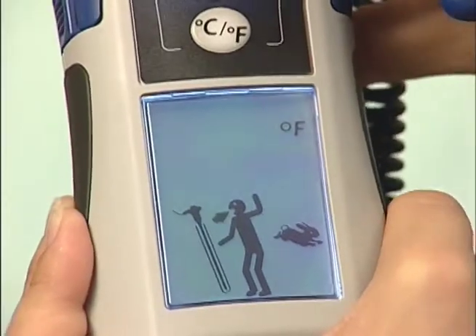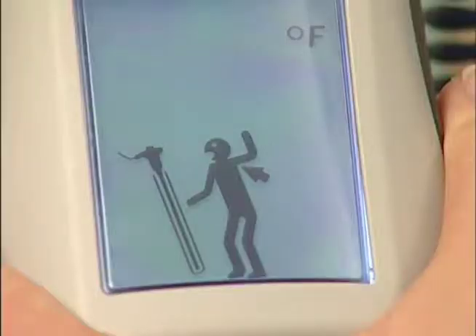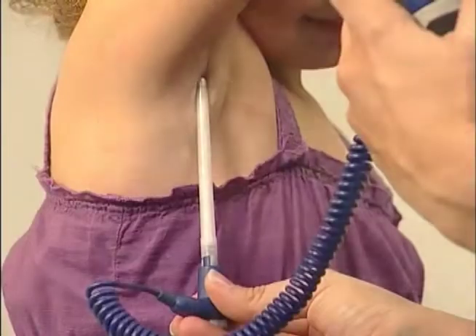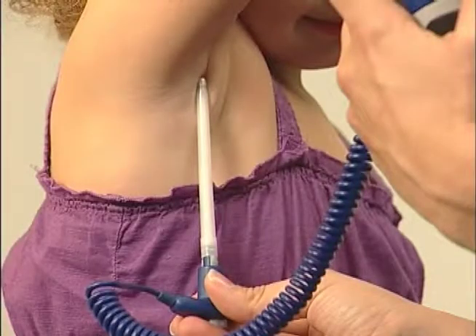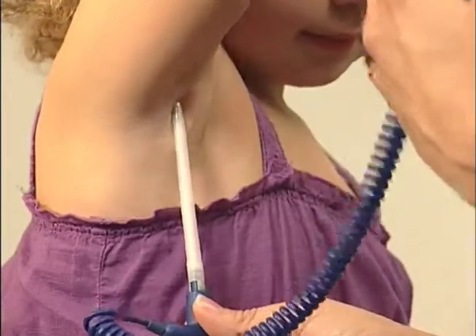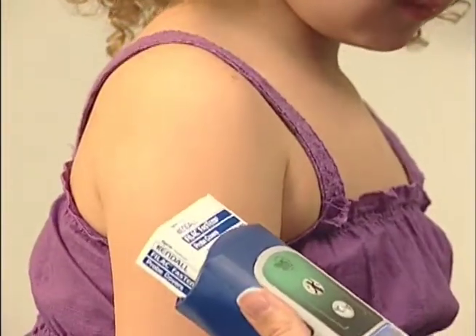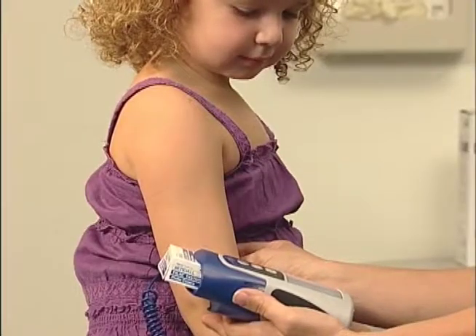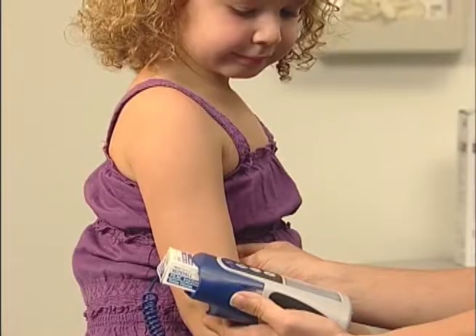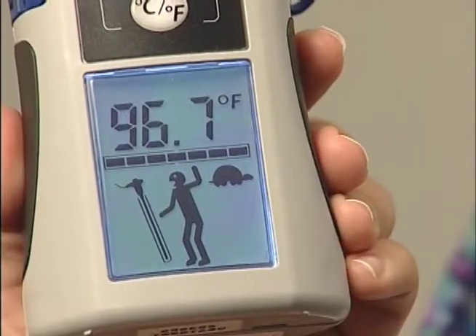To take an axillary temperature, use the blue isolation chamber. Ensure the thermometer is in axillary mode. Raise the patient's arm and place the probe tip directly against the skin, in the center of the axilla, parallel to the spine. Press the probe gently in place to ensure good contact. Lower the arm and have the patient remain as still as possible. Hold the probe in place until a long beep sounds, indicating the temperature measurement is complete and the final reading is displayed.